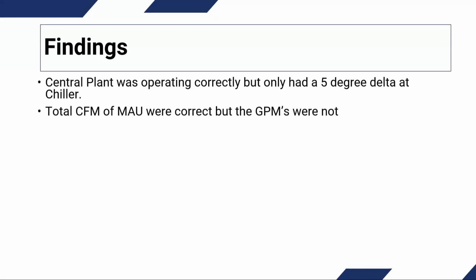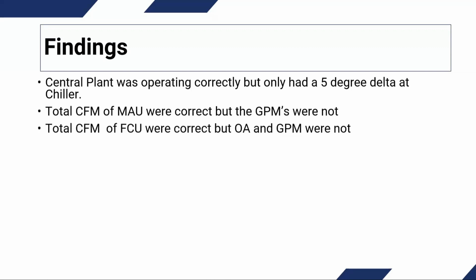When we looked at the makeup air units, total CFM of the makeup air units were all correct. They looked good, but when we measured the GPMs, they did not match the submitted GPM rating for the makeup air units. On the fan coil units, the total CFM seemed to be correct, but the outside air was not correct going to each one of the fan coil units. So it appeared that the makeup air units were set for total, but they weren't proportioned to the fan coil units. And again, the GPMs were not within design parameters.